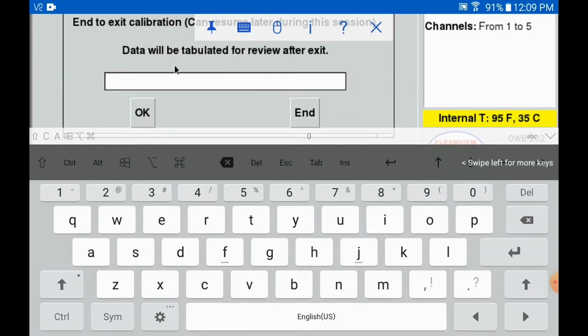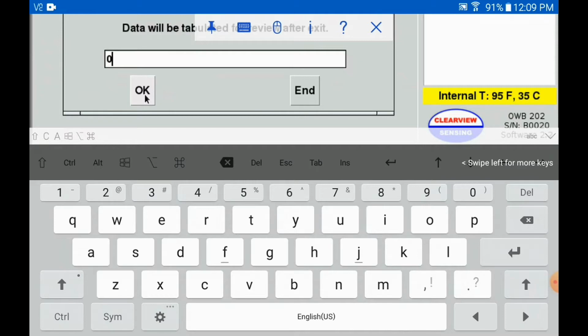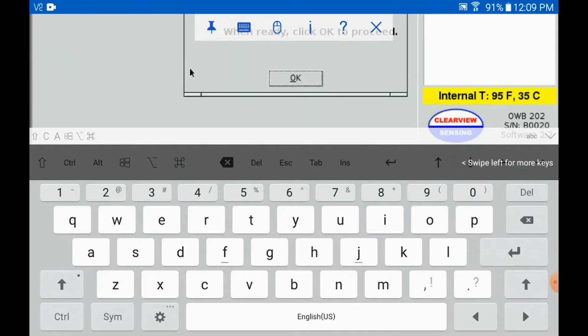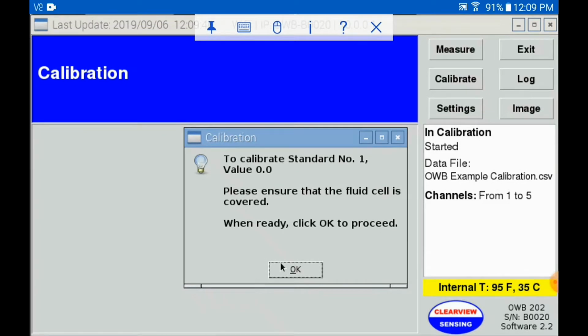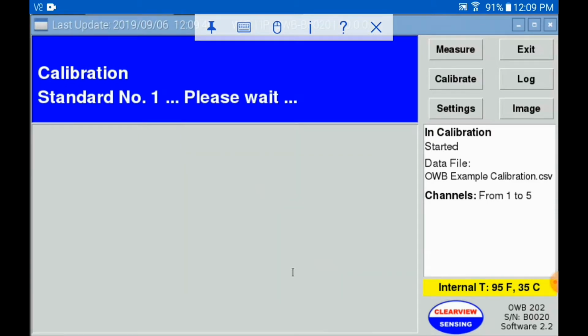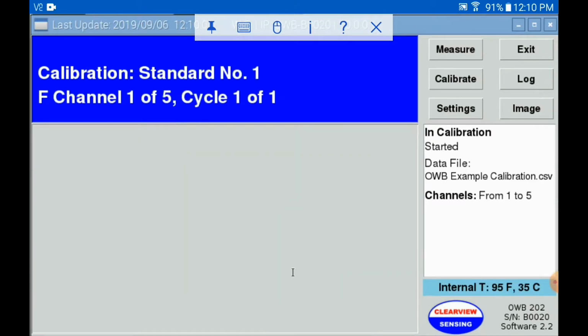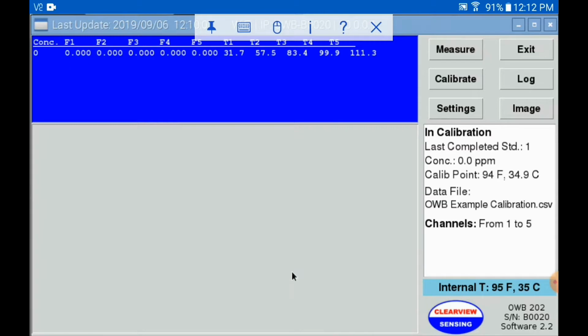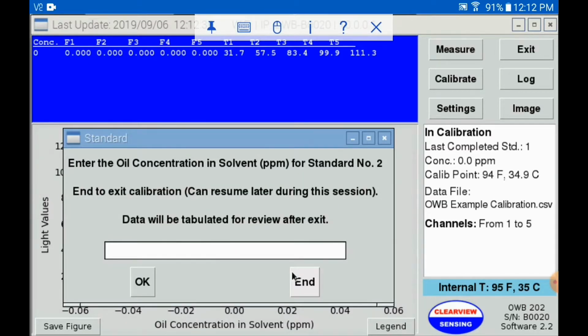The calibration value can now be entered, 0 ppm in this example. The keyboard can now be downsized. Please be sure to cover the cuvette cell with the cap before beginning calibration. OWB calibration will cycle through 5 fluorescence channels and 5 transmitted light channels for each calibration point. I'll skip forward to the end. After the calibration point is complete, the values for fluorescence and transmitted light can be seen for each channel in the upper portion of the screen. Now the next standard can be calibrated.